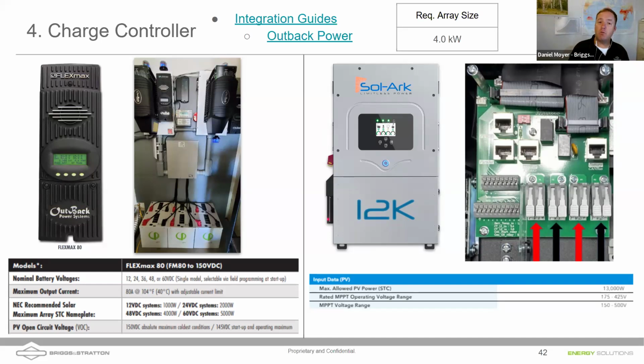We've got a 4,000 watt array. As long as we're working at 48 volts here, we can use our charge controller, that Outback, or we could probably bump it up to the FM 100. That Sol-Ark unit can handle 13,000 watts, so absolutely we can still use it. We need to make sure our charge controllers are capable of handling all the photovoltaic panels we're putting into the system.